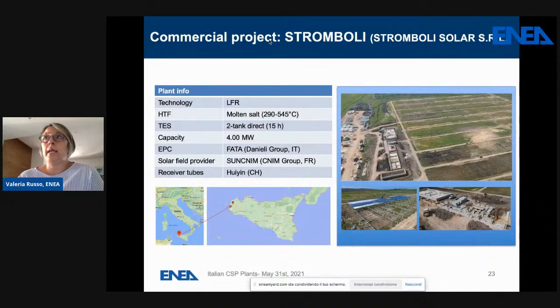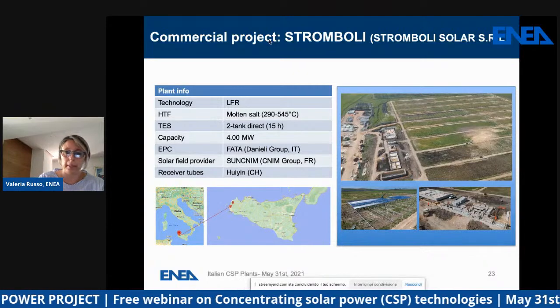Now we can talk about the other plant, called Stromboli. This plant is equal to the Partanna plant. It is situated also in Sicily, near Trapani. The technology for the solar collector is the same used in Partanna, the linear Fresnel collector. The heat transfer fluid is molten salt, and also in this case we have a direct thermal energy storage with 2 tanks, and the capacity of this plant is equal to 4 electric megawatts. Also in this case the EPC contractor is FATA, but here the solar field is provided by SUNCNIM, part of the CNIM group from France, and the receiver tubes are provided by Huiyin, a Chinese company.